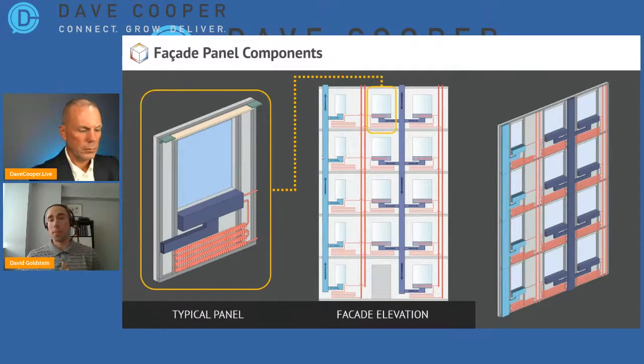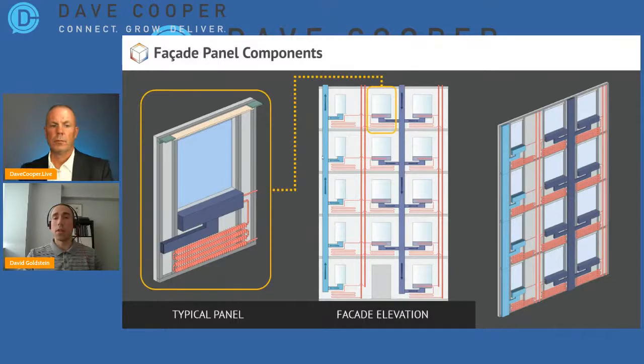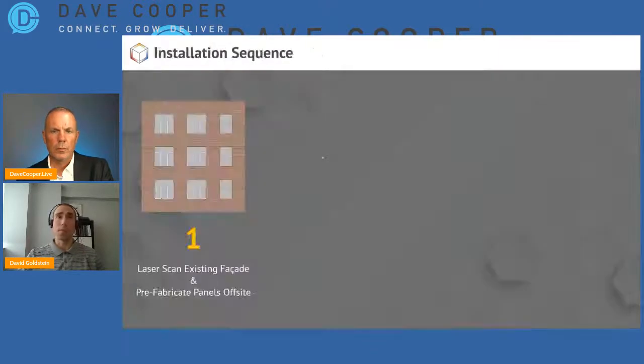If the bathrooms and kitchens are not at the perimeter, if they're interior, that building will already have some sort of exhaust system, because you need one if you don't have perimeter windows. So we would tap into that existing exhaust system at the roof. The idea is we're taking that exhaust and running it through energy recovery, so that when we condition the fresh air, we're not consuming as much energy.